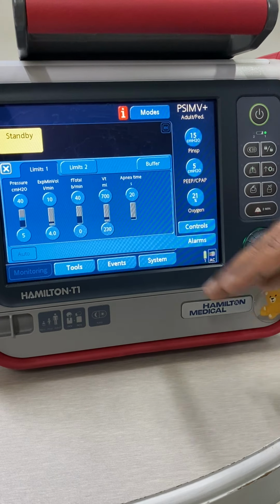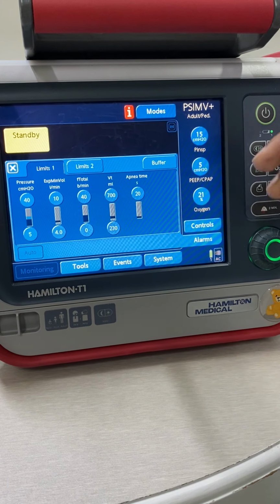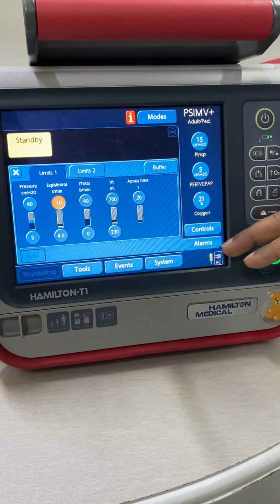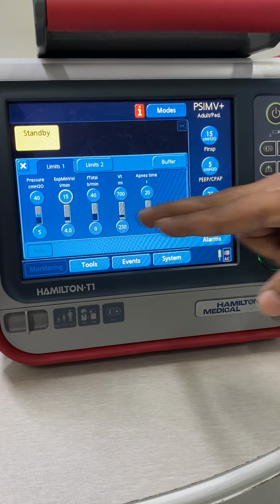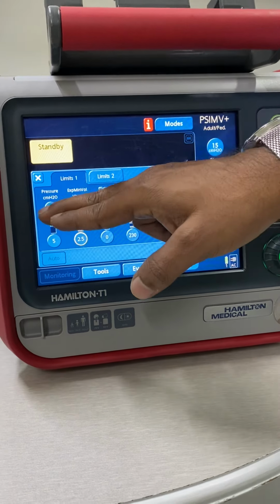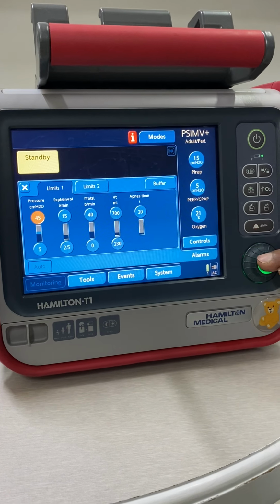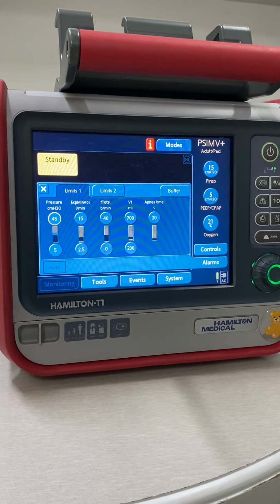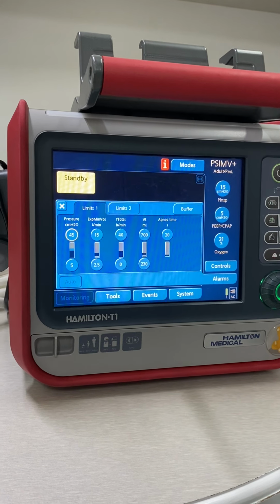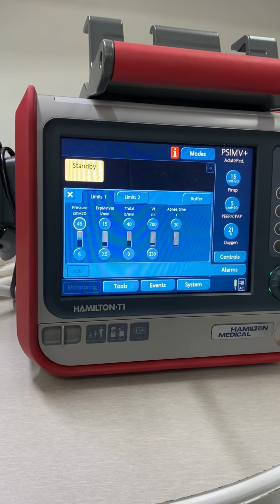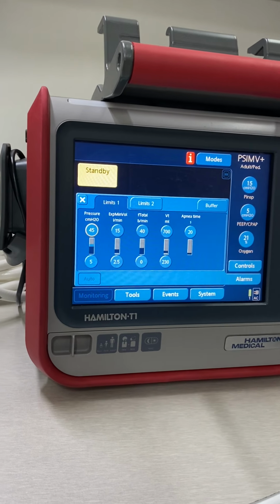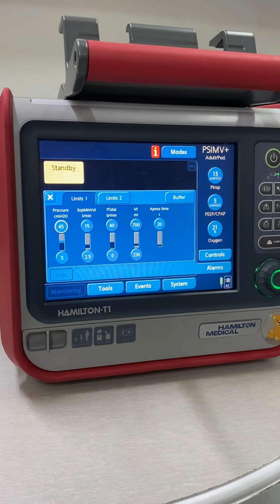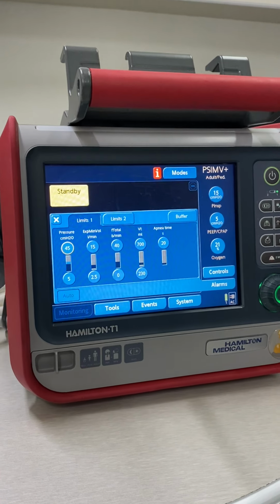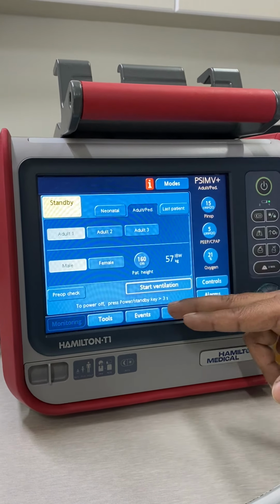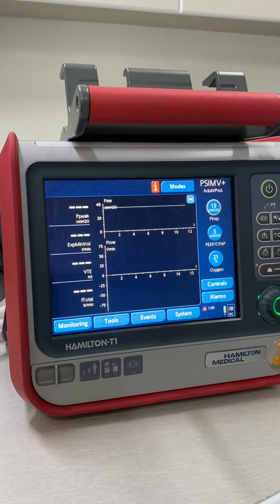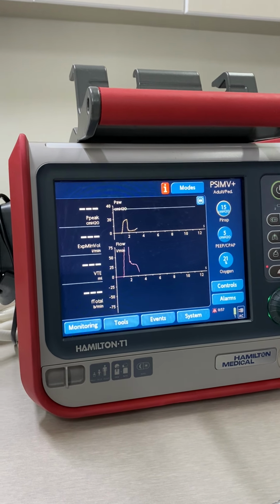Then you can go to the alarms and adjust the alarm limits according to your current settings. So you can set up the expiratory minute volume upper limit and the lower limit according to your current setting. Pressure limit also here as a pressure cap. Okay, so you will adjust the alarm limits, then you can go to start ventilation.